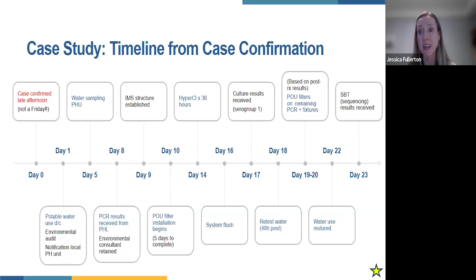This was considered an internal emergency for us, and we had emergency management supporting us, which was instrumental to our response - through the hyperchlorination process and finally receiving our final sequence-based type testing. So we're looking at about 23 days of no water. Having these high-risk units without water for that length of time is a massive risk in itself. When determining the right time to turn water back on, you really have to do a risk assessment based on who's in the building, your patient populations, and the risk of not having water to those areas.